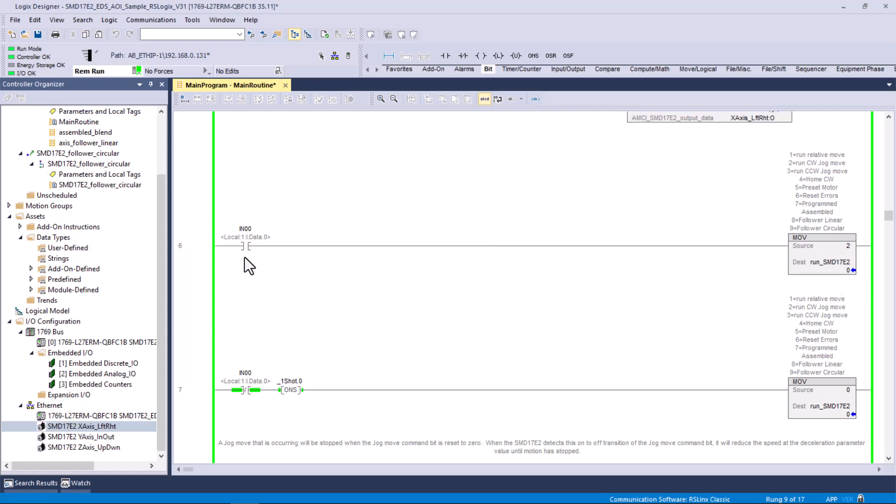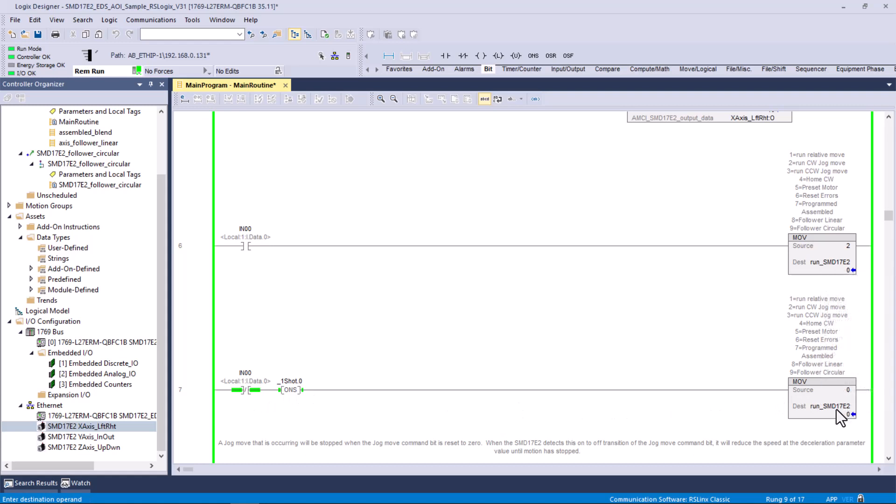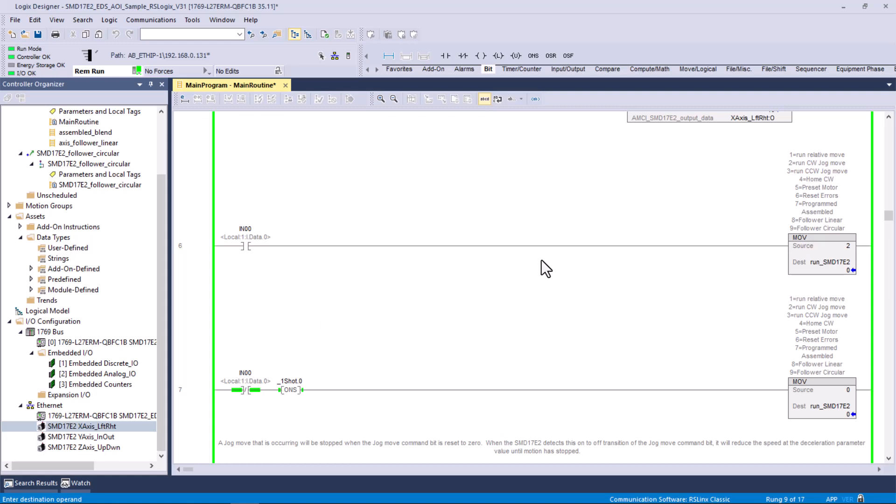I added two rungs of logic, and I attached the instruction that moves a two into this register. I'm controlling it with input zero on my digital field device simulator. And then when I release the button, I have a one-shot that puts a zero back into this run command. In a lot of cases, once you turn the dogs loose, they're loose. If I put a two in there, even though I let go of this button, the two's gonna stay there, and it's gonna keep jogging. If you want it to jog when you push the button, and then when you release the button, stop jogging, then when it goes false, you one-shot a zero in there.